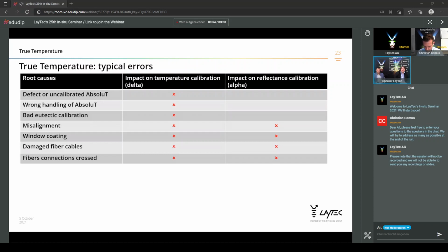In principle, you may get the impression at first glance that the EpiTT is still working, but in fact the entire balancing and calibration and consistency of the amount of light is completely disturbed with crossed fibers. So as a side effect, this will definitely have an impact on delta and alpha calibration. The calibration sequences will still run and reveal a delta and alpha result, but the results will definitely be wrong. And that will definitely ruin any true temperature in the system.